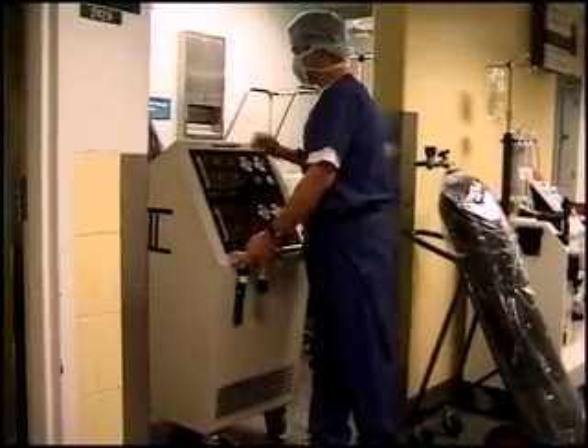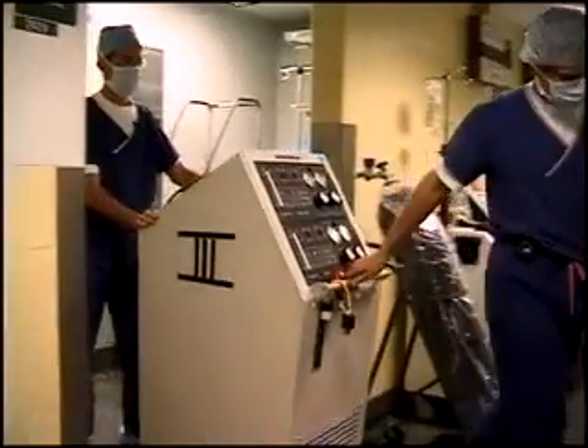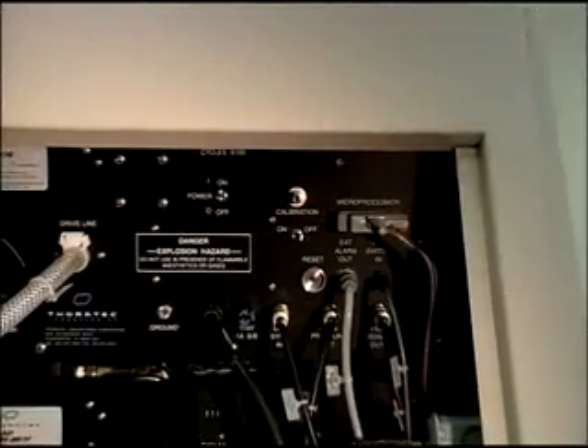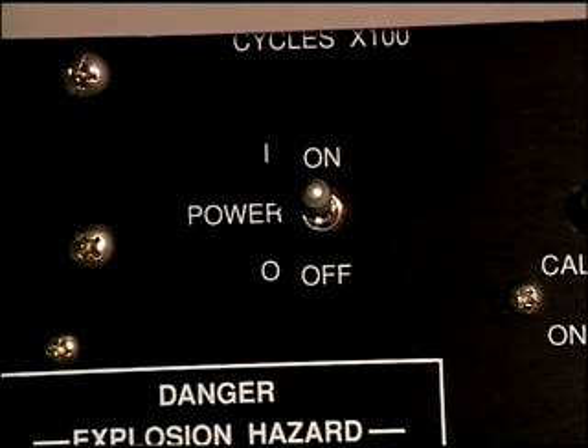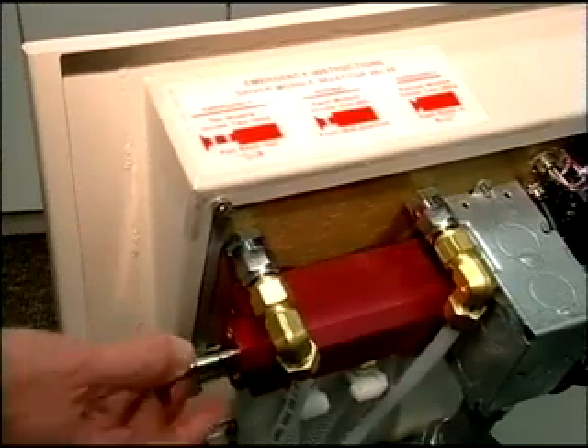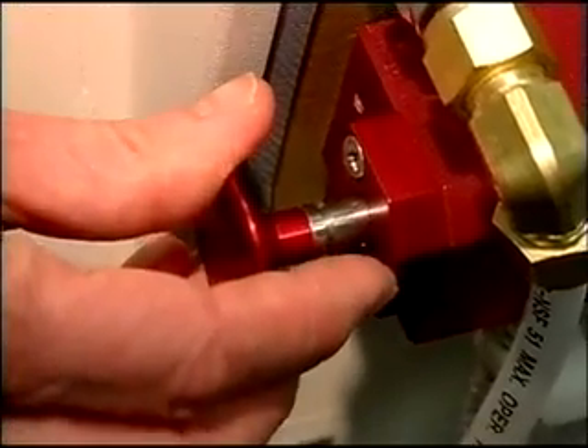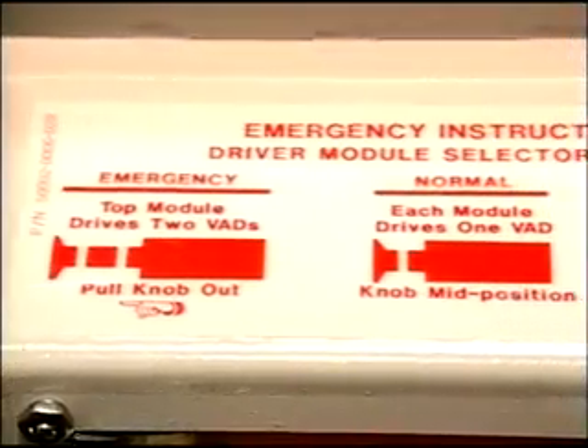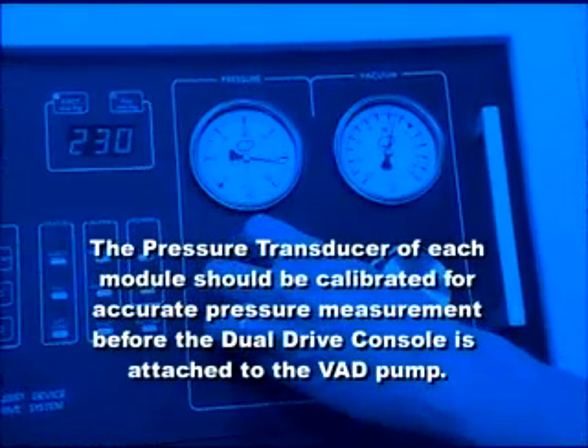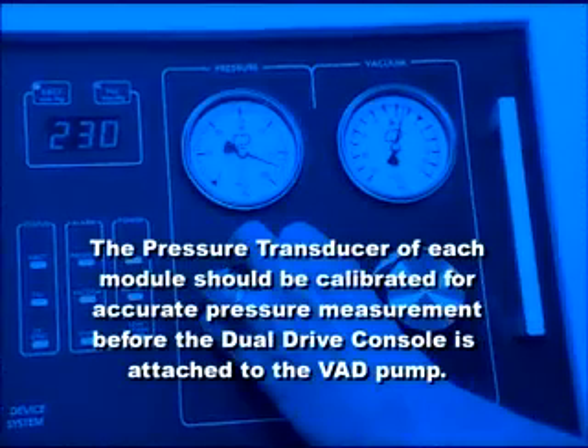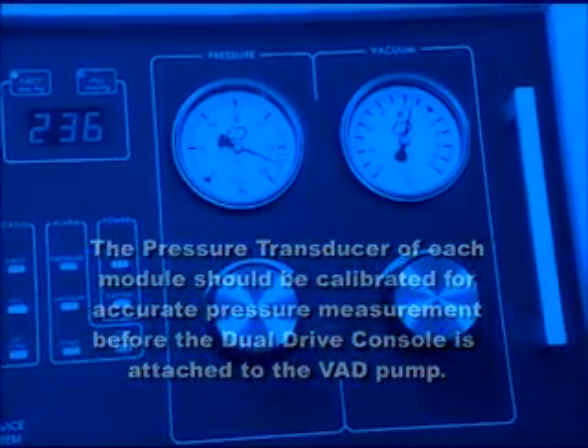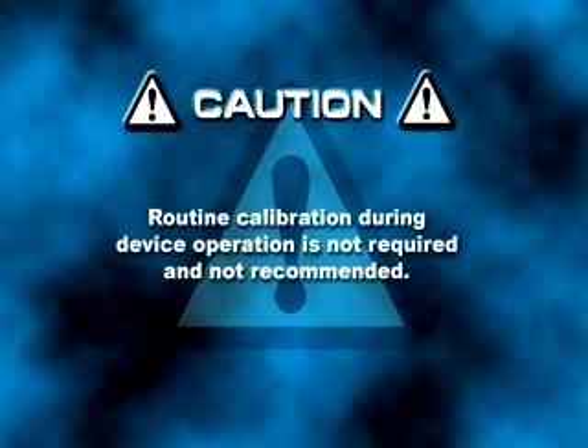When the console is brought out of storage and ready for use near or within the operating room, open the console's back door and turn the top and bottom module's power switches to the on position. These are toggle switches which must be pulled out and then up. The selector valve should be in the center position. This valve is for short-term emergency use and allows one module to pump both VADs. Next, the pressure transducer of each module should be calibrated for accurate pressure measurement before the console is attached to the VAD pump. Routine calibration during device operation is not required and not recommended.